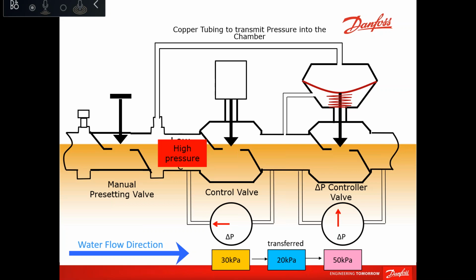But in most cases, you can just fully open it in order not to do a lot of big work, because usually a PICV will fit directly on a two-way valve. If you remove a two-way valve and put in a PICV, it's nearly the same size. If you match the size, it will be the same width. So sometimes they ask why we should remove the DRV, just open it fully. Yes, it is possible, since most of the time the DRV's pressure drop is very low, so you can fully open the DRV and keep it. But if the PICV plus DRV is higher than the existing two-way plus DRV, then it is better to remove the DRV to reduce it.